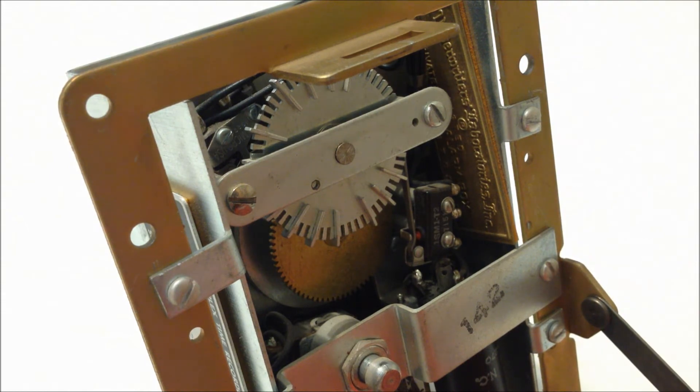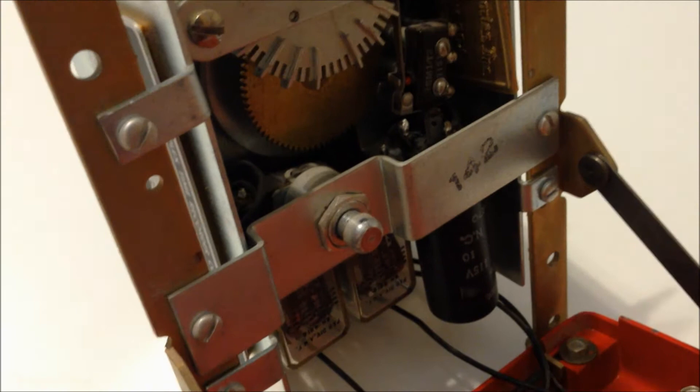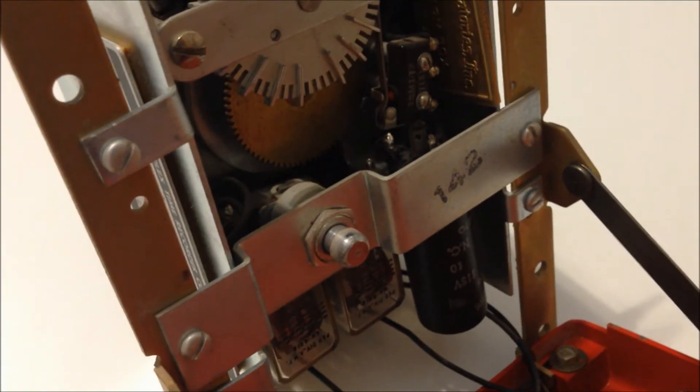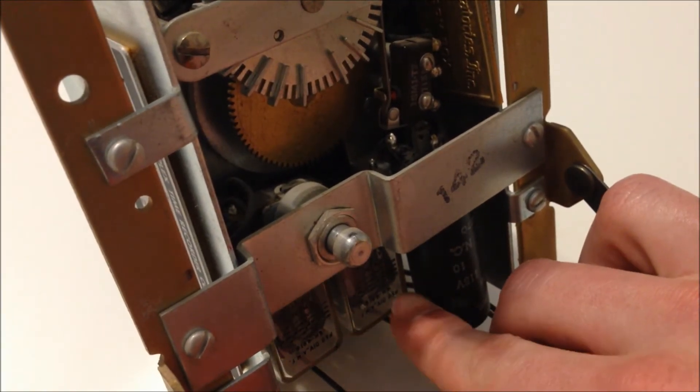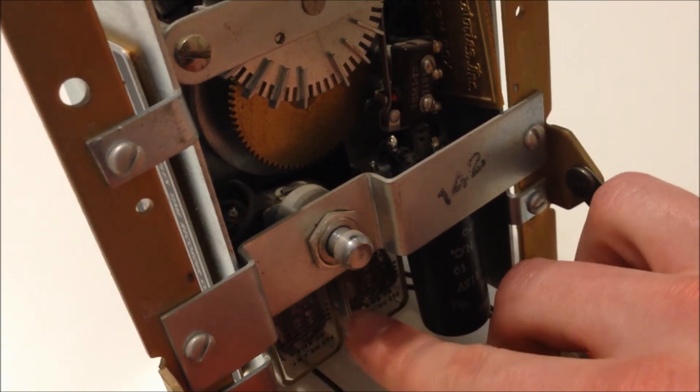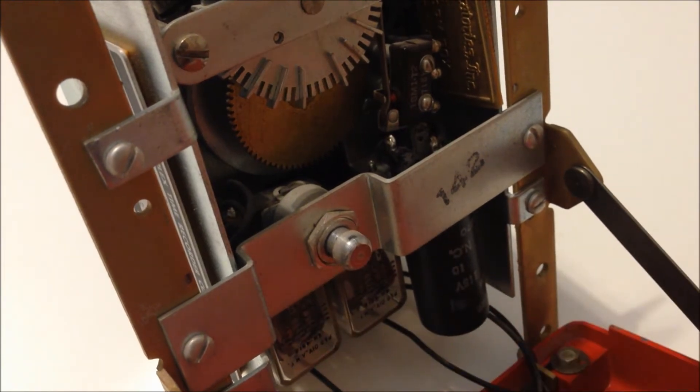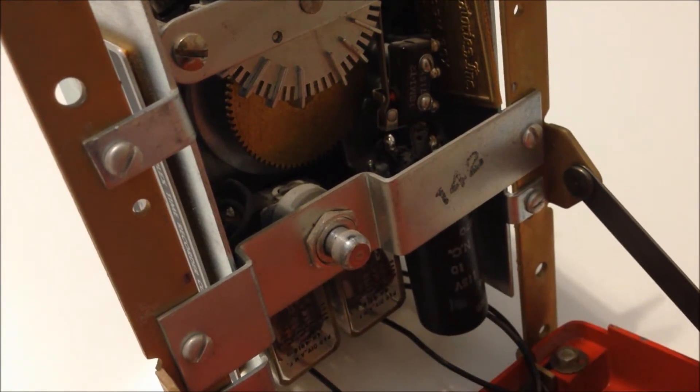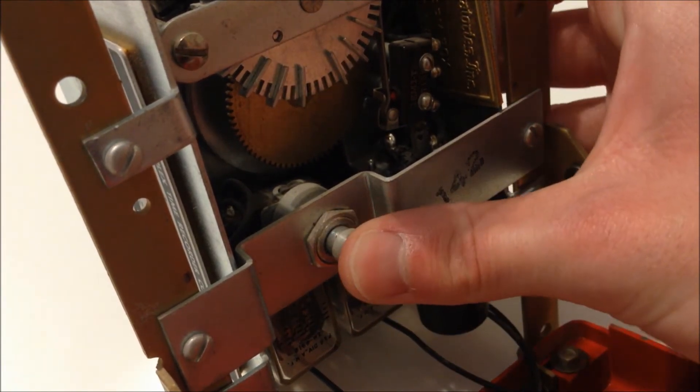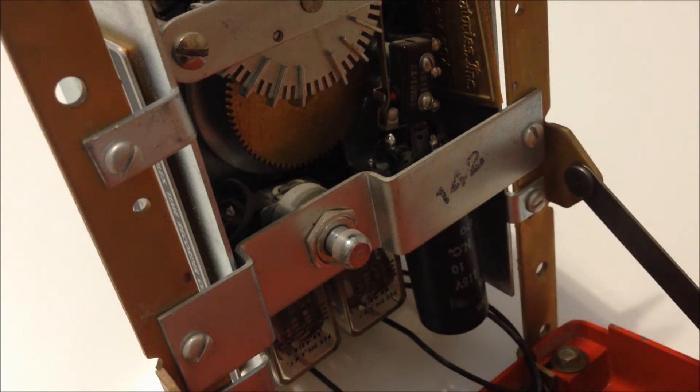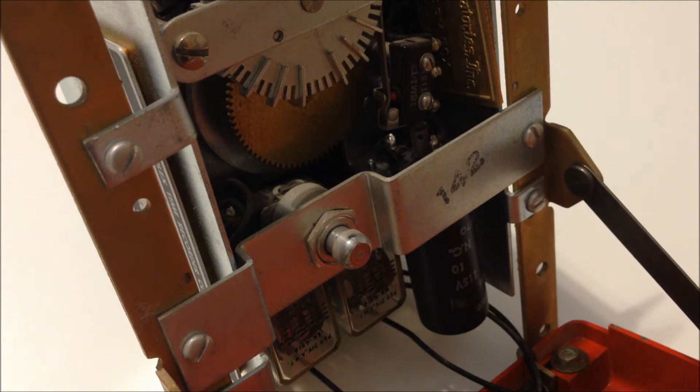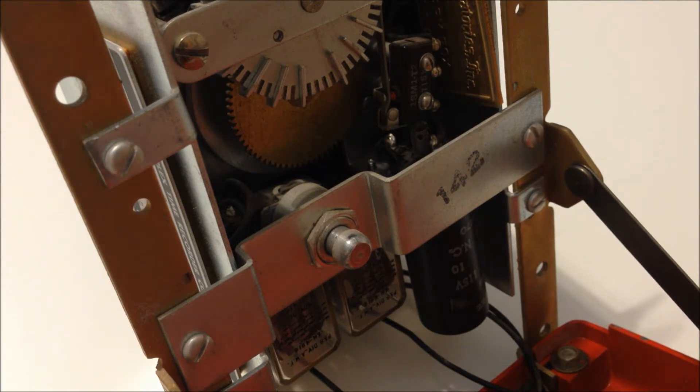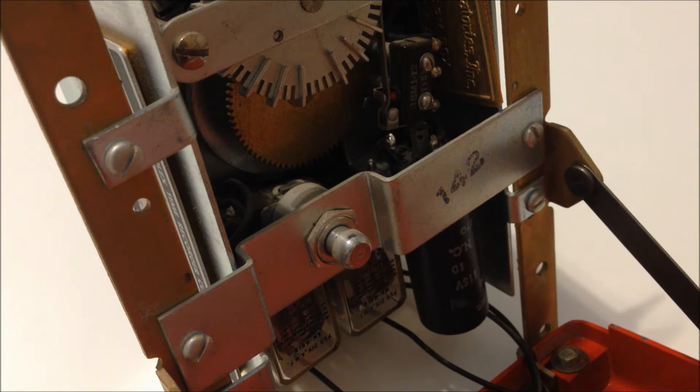If we move the frame down here just a bit you can see one of these two relays that I was just talking about is what connects to the micro switch. You'll see that there's the standard push button on this assembly that looks just like the interior of one of these non-coded pull stations, and that's essentially what this is. The entire front half of this unit is just a non-coded pull station that we're used to seeing from that era, and then this entire coding module has been added on to the back.